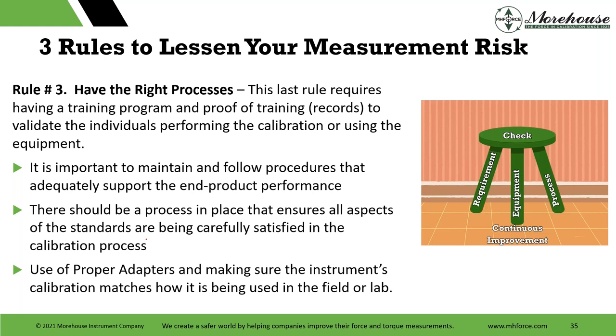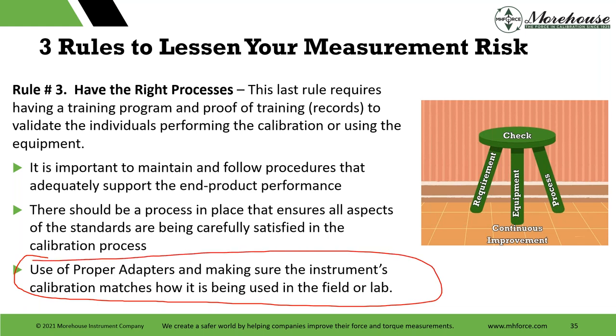Back to the right process: it's important to maintain and follow procedures that adequately support the end product performance. There should be a process in place that ensures all aspects of standards are carefully satisfied in the calibration process. For force specifically, and in some other mechanical and electrical disciplines: your contacts, what you're using, use of proper adapters, and making sure the instrument's calibration matches how it's being used in the field or lab. We do classes on adapters, and some of those errors can push 20 times that of manufacturer's specification — some push 50 times the manufacturer's specification.